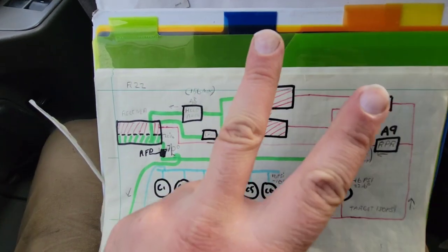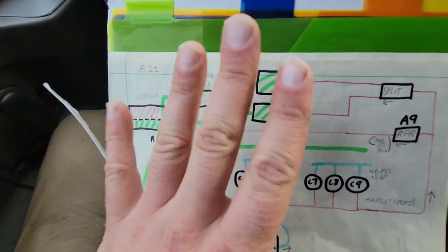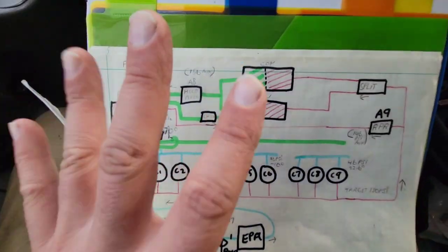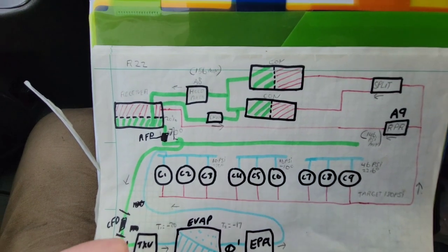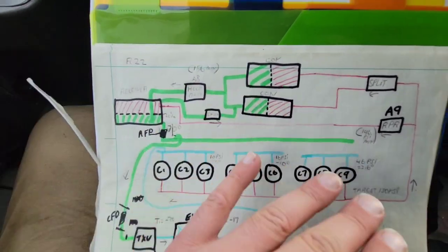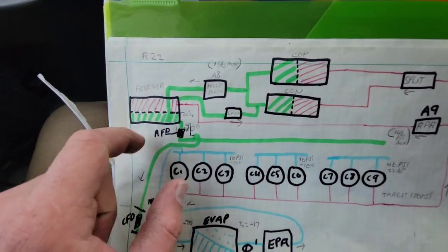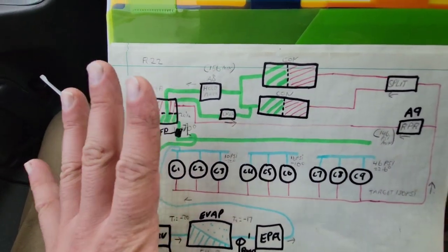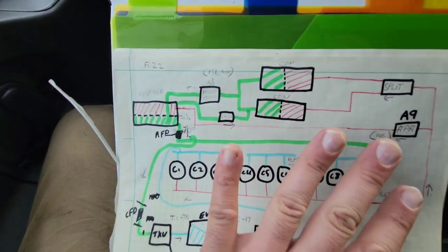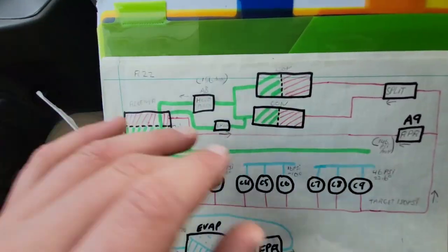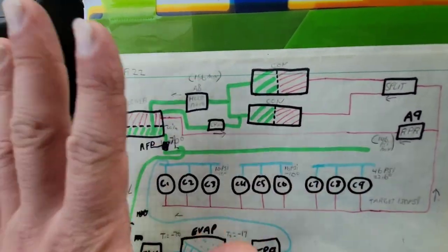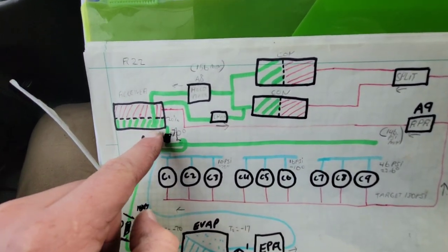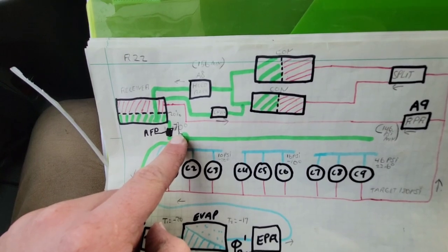Now, there is a slight caveat here, kind of difficult, but sometimes your sight glass will still flash in the winterish months, because there's not a high enough load and there's not enough flow. So you'll still have a receiver level, you'll have no pressure differential, and you might have a sight glass that flashes and then disappears and then flashes. Sometimes that happens, but it's not super common. But the general rule is: receiver level, clear sight glass, no pressure differential across the filter dryer.